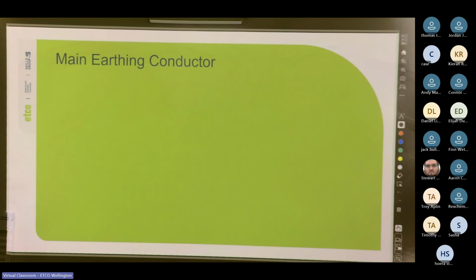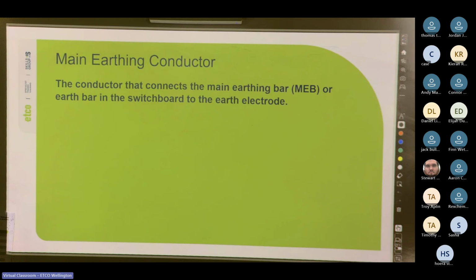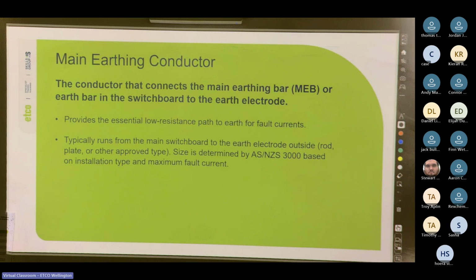Yeah. Cool. So main earthing conductor. It's the conductor that connects the main earthing bar, MEB, or earth bar in the switchboard to the earth electrode. That is what our earthing conductor is. So it provides an essential low resistance path to earth for fault current. It typically runs from the main switchboard to the earth electrode. It can be a rod, a plate, or any other approved type. And the size is determined by 3000 based on the installation type. And it's the backbone of our protective earthing system. Without it, the MEN link has no return path.